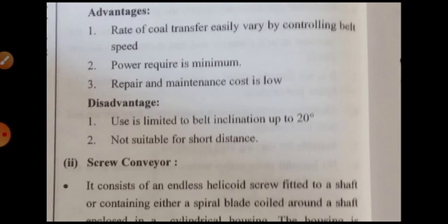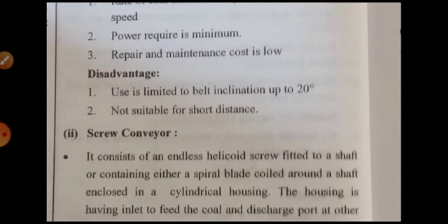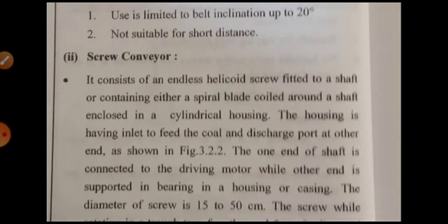Advantages: the rate of coal transfer can easily be varied by controlling the belt speed. Power requirement is minimum. Repair and maintenance cost is low. Disadvantages: its use is limited to inclination up to 20 degrees, and it is not suitable for short distances.